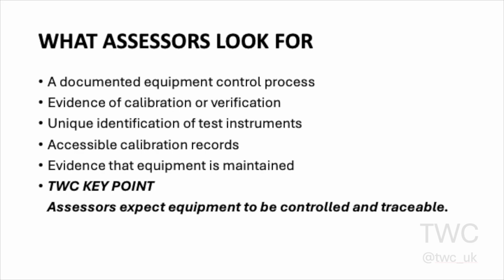Assessors typically look for evidence that test equipment is being actively managed. This may include equipment registers, calibration records, verification records, and procedures that identify how instruments are controlled. The key point is that assessors are looking for a system. They want to see that equipment is identified, traceable, and supported by appropriate records rather than simply assuming that instruments remain accurate indefinitely.